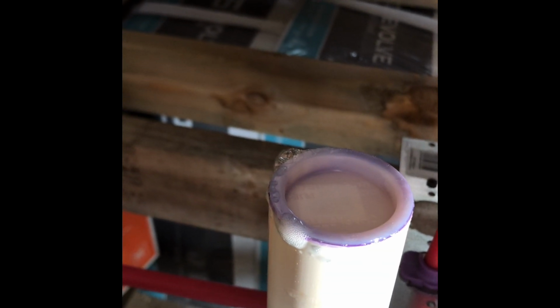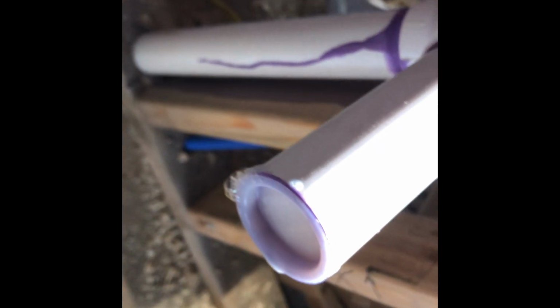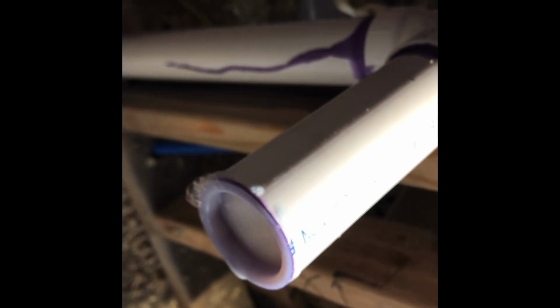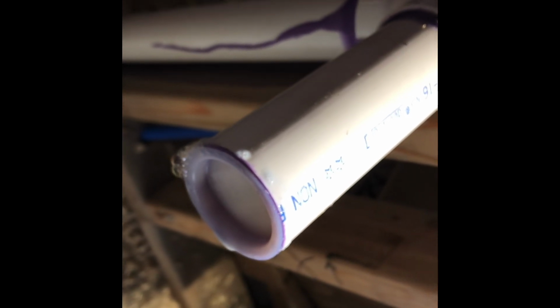Also, I see something over here. I'm not real sure. See if we can get it to focus. Get my finger out of the way. There's some more bubbles right there. There's a patch of bubbles. So we got several leaks maybe in this little test cap here. It doesn't have a whole lot of glue area on it, so we'll cut that off. We'll put a different type of test cap on there and recheck it.